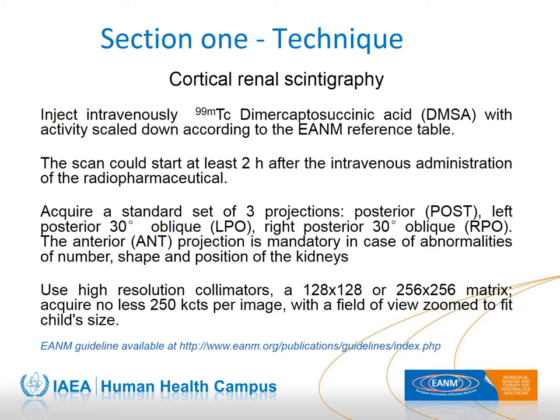The anterior projection is much more difficult to acquire because you must either place the camera surface close to the child's face or place the child in a prone position — both positions are uncomfortable. Each image must contain at least 250 kcounts, although 200 can be enough for the oblique. It is useful to also set a camera stop at 600 seconds. The recommended matrix is 256 by 256, although 128 by 128 is acceptable, especially when you reduce the field of view by zooming and the pixel size is less than 2 millimeters, as happens with a field of view no larger than 25 centimeters.